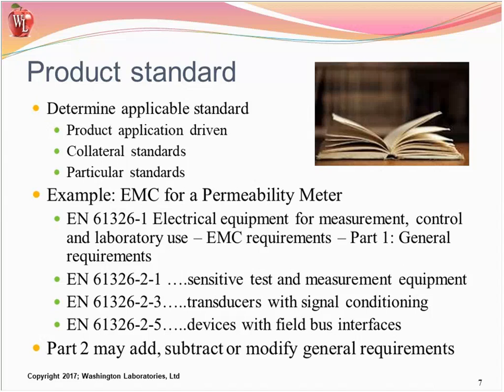I've got an example for EMC for a permeability meter, something that measures the ferrous metal content or permeability of a particular material. 61326-2-1 applies to sensitive test and measurement equipment. So I may have a very sensitive device trying to develop a measurement of a magnetic field. Naturally, if I apply magnetic immunity requirements to this, it's probably going to fail because it's built to measure magnetic fields, and a stray magnetic field will cause it to react. So this is something that has some specific guidelines.